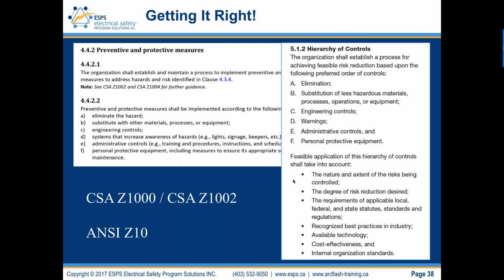So we do want to do these arc flash energy analysis studies, and we want to use that information to look at mitigation. Mitigation that's technically feasible and cost effective, or costs are managed. We still have to have economics considered when we do engineering. So there's a cost benefit analysis to mitigation, right? So we want to apply all the controls. I'd love to engineer out the arcing fault arc flash hazard, but with all the existing equipment, we just can't do that right now. In the future, it will be a different discussion.